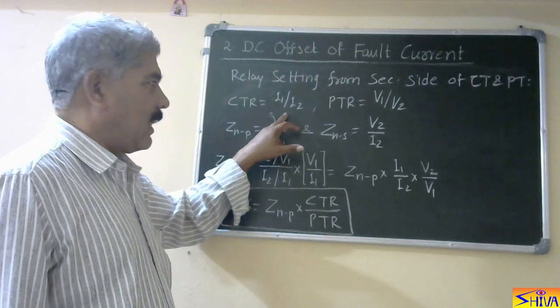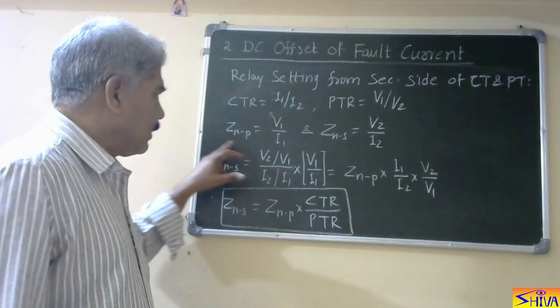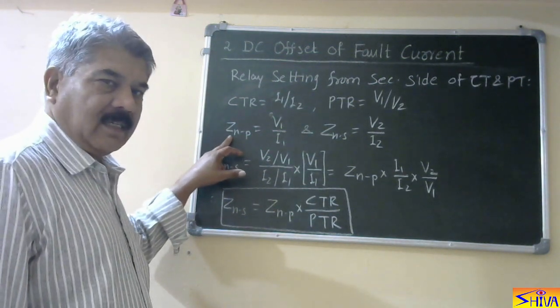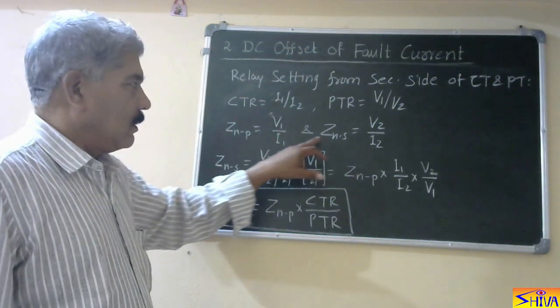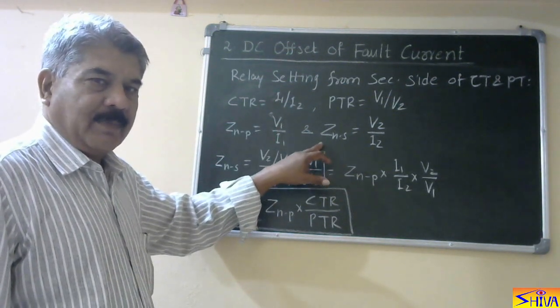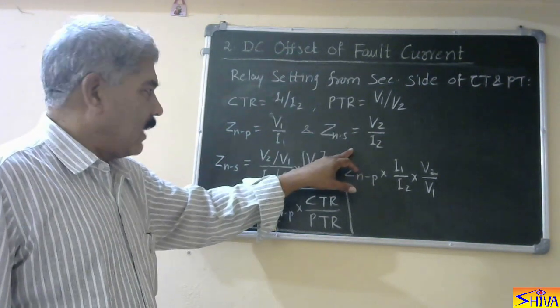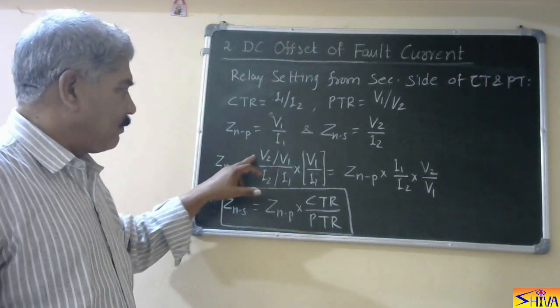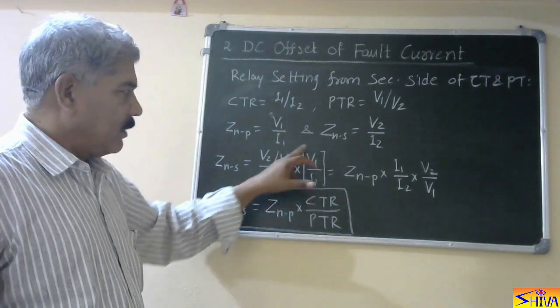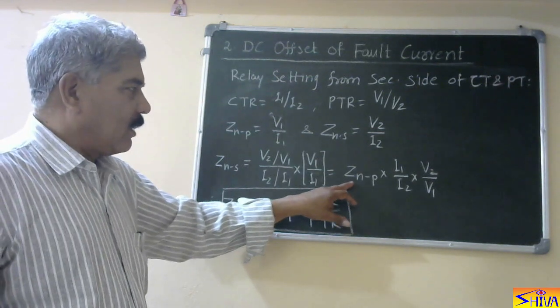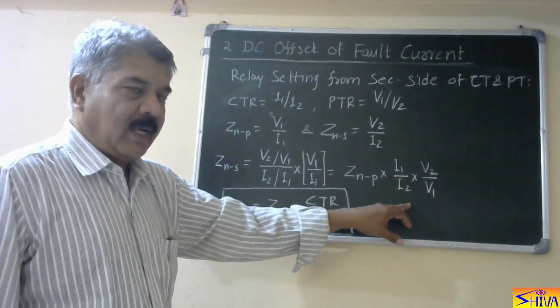Let us say CT ratio is I1 by I2, and PT ratio is V1 by V2. The primary side setting Zn — the reach of the relay or impedance setting from the primary side — is V1 upon I1. Zns, the impedance setting or reach from the relay side, is V2 upon I2. This can be written as (V2/V1) divided by (I2/I1) into V1/I1, which equals V1/I1 multiplied by I1/I2 into V2/V1.